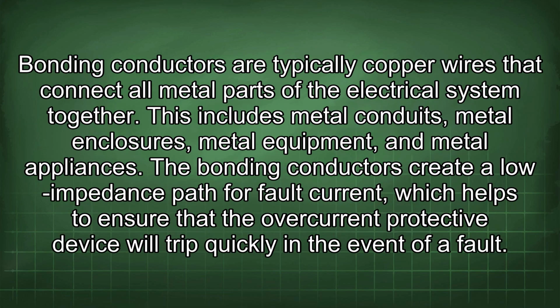Bonding conductors are typically copper wires that connect all metal parts of the electrical system together. This includes metal conduits, metal enclosures, metal equipment, and metal appliances. The bonding conductors create a low impedance path for fault current, which helps to ensure that the overcurrent protective device will trip quickly in the event of a fault.